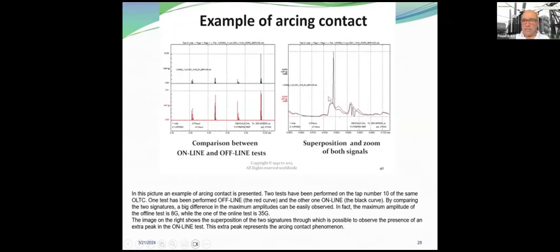So here, this is a zoom of these two, the last impact, the last peak. The image on the right shows the superposition of the two signatures, through which it is possible to observe the presence of an extra peak in the online test, and this extra peak represents the arcing contact phenomenon.